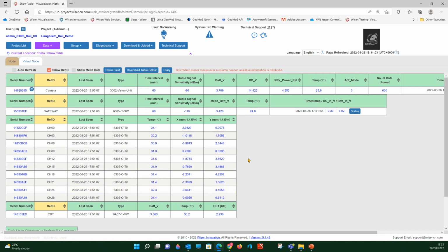The next stage, obviously, you would have data collected over a baseline or commissioning period, and you would be looking to offset those absolute values. So in essence, they start from a relative reference value, and that is normally 0. Now I've done that previously on this job, but for the purpose of this video, we are going to treat this as if we're also undertaking that process.